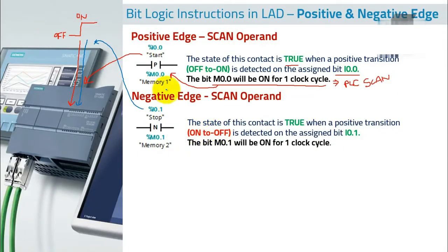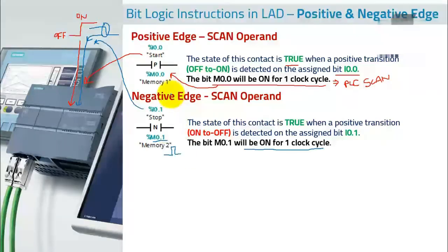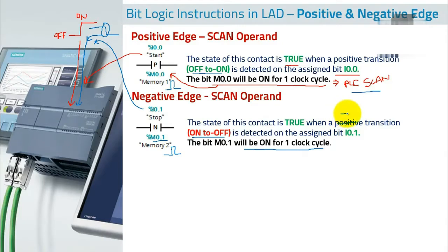If this input has an on-to-off transition — meaning if it is already on and then goes off — at that particular instant, bit M0.1 will be on for one clock cycle. In both cases you get a pulse, its duration equivalent to the PLC scan time. But for the positive edge the pulse occurs on off-to-on transition, and for the negative edge it's a negative transition.